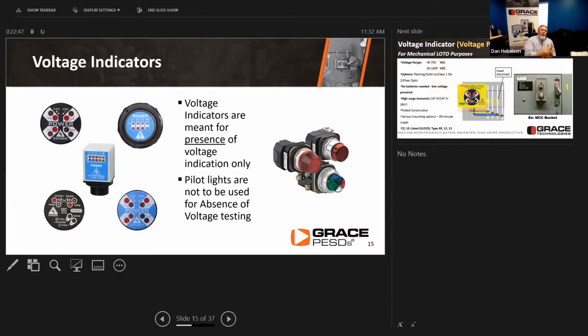What this is doing is showing that there is voltage present on those three phases. There is no voltage showing on the ground, and that's all this device does, is it measures phase to phase and phase to ground all the time. And it just gives you an opportunity to do some troubleshooting and take a look at your equipment and see what may be happening inside that equipment.